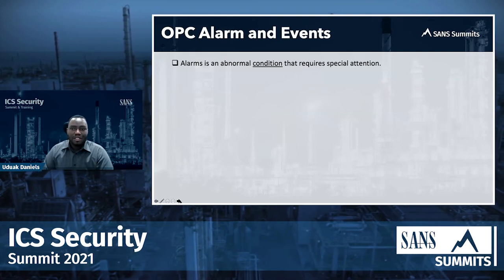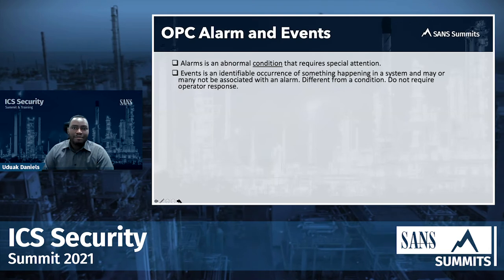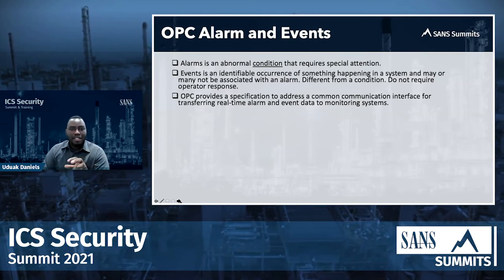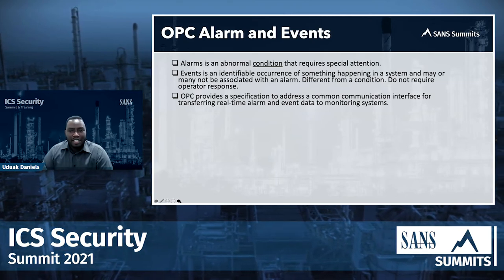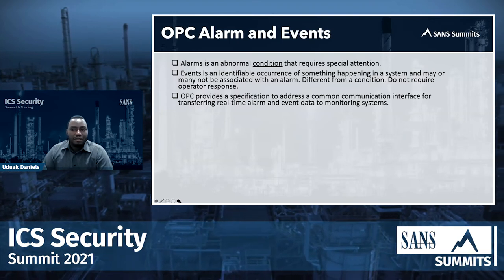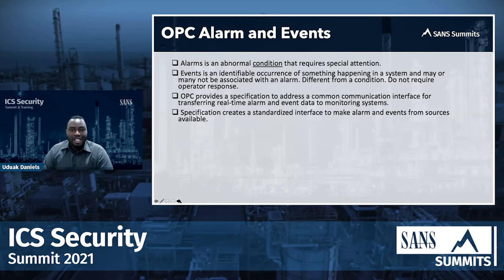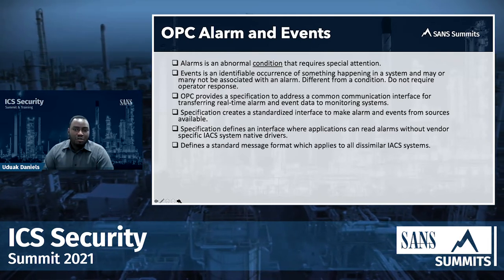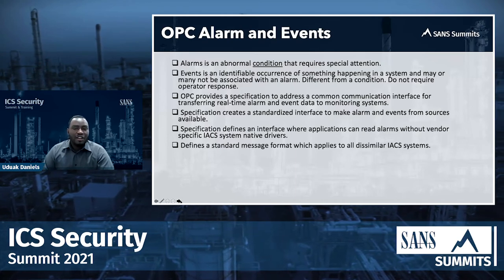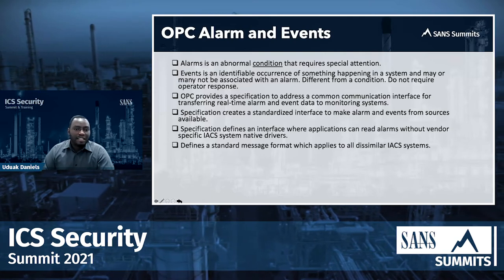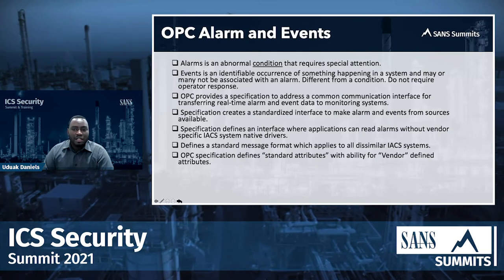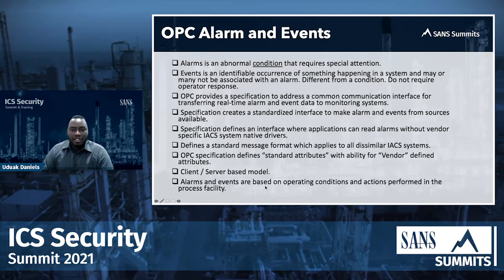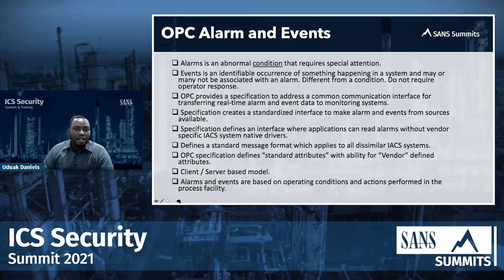OPC alarms are abnormal conditions; events are identifiable occurrences of something happening. OPC provides a specification to address a common communication interface — the great feature about OPC is its commonality. For those new to ICS, it provides real-time alarm and event data monitoring on pretty much all systems. It defines a standard message format that can be leveraged in any industry — whether oil and gas or others — standardized across all different industrial control systems environments. It's a client-server-based model, so it fits into any Ethernet-type environment.